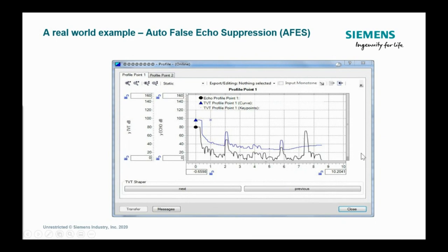Well, there's the beauty in the instrument itself. When you're looking at auto false echo suppression, it doesn't just learn where these echoes are, but it learns the signature of those echoes. And the signature off of, in this case, a bell end, or maybe you have an open tank and you have a cross member or rail or a weld seam on the side of a tank or something like that, the echo off of a steel pipe is different than the echo off of the material. So it learns what you're trying to measure and it learns where these things are. And so if this echo happens to migrate here to the left and it happens to stop right there where you've mapped that out, it will still follow your true echo, because the signature of this one and the signature of what it mapped out are different. That is something that is unique to Siemens as part of that process intelligence.